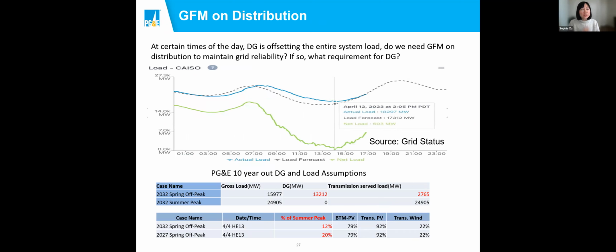So basically, in addition to a lot of things I tested on transmission connected inverter-based resource, distribution is also, DG is also growing very fast in California. And the top plot is what we saw just a few days ago, April the 12th, the net load on California ISO is almost zero. It's only 600 megawatts because pretty much almost all the gross load is offset by the DG, the distributed generation. So imagine at some point, from time to time, almost every day in the future, the grid is being served both on the demand and the reliability by the distributed energy resource. Then the DG needs to take on all the reliability service responsibilities instead of the transmission. So this is another big task.